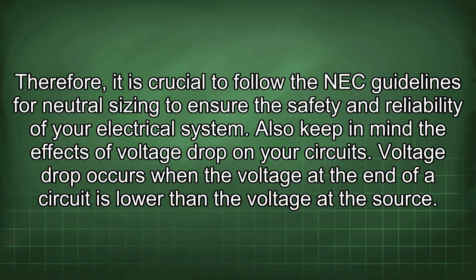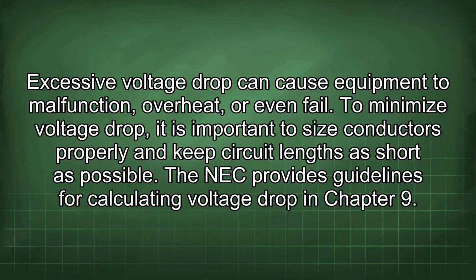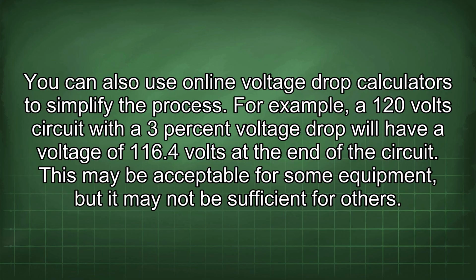Voltage drop occurs when the voltage at the end of a circuit is lower than the voltage at the source. Excessive voltage drop can cause equipment to malfunction, overheat, or even fail. To minimize voltage drop, it is important to size conductors properly and keep circuit lengths as short as possible. The NEC provides guidelines for calculating voltage drop in Chapter 9. You can also use online voltage drop calculators to simplify the process.